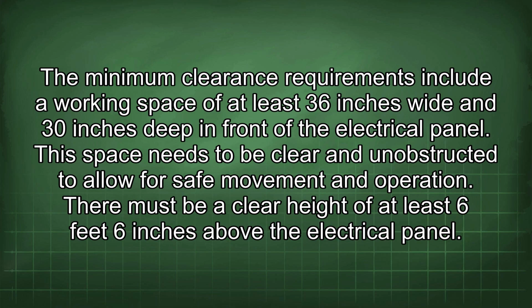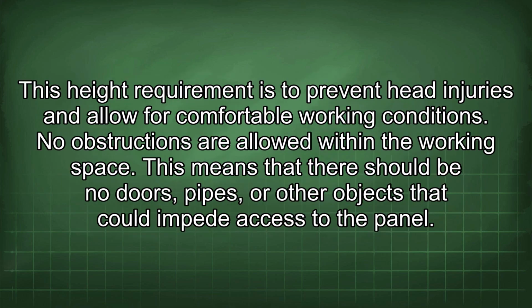There must be a clear height of at least 6 feet 6 inches above the electrical panel. This height requirement is to prevent head injuries and allow for comfortable working conditions. No obstructions are allowed within the working space. This means that there should be no doors, pipes, or other objects that could impede access to the panel.